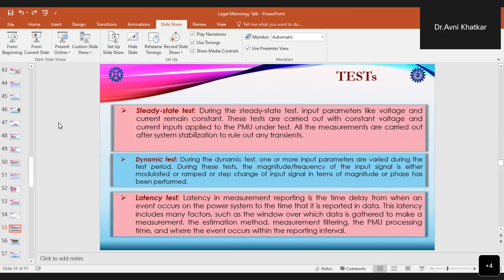Whereas in the dynamic test, one or more input parameters are varied during the test period. In this test, the magnitude or frequency of the input signal is either modulated or ramped, or a step change of the input signal is done in terms of the magnitude or phase. So depending upon the different type of dynamic test, the magnitude or frequency of the input signal is changed.